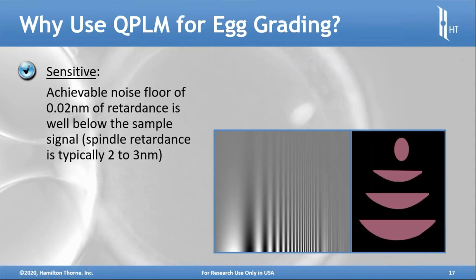It's sensitive down to 0.02 nanometers of retardance. Retardance can be defined as the way light passing through highly organized molecules is attenuated under different polarized states. The spindle — the microtubules containing the chromosomal complement inside an oocyte — are highly ordered molecularly and present a spindle retardance in a range of two to three nanometers typically, well above the noise floor of the tool.